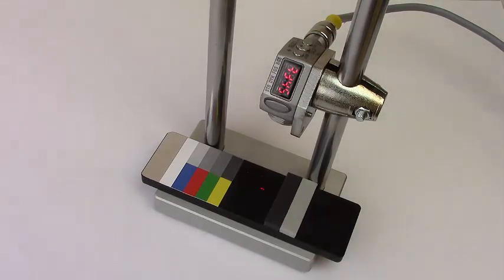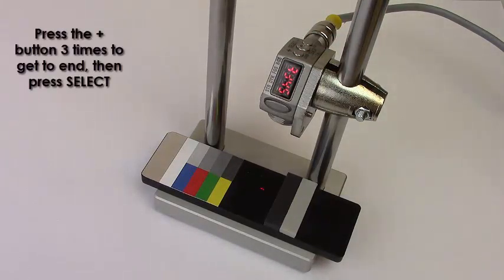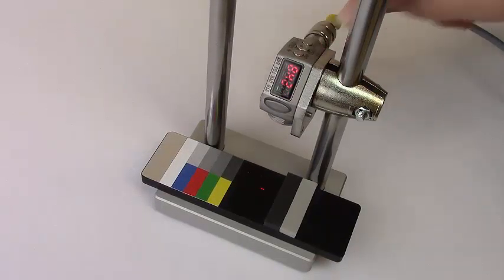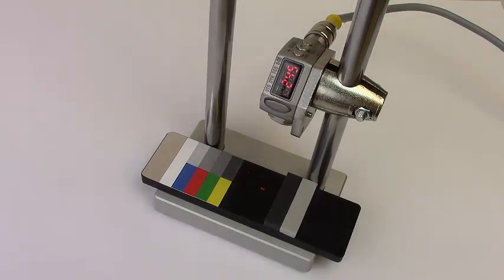Press the plus button three times to get to end, then press select. After switching the zero reference point, the distance from the target to the sensor is now 245 millimeters, which is 300 minus the previous measured distance of 55 millimeters.